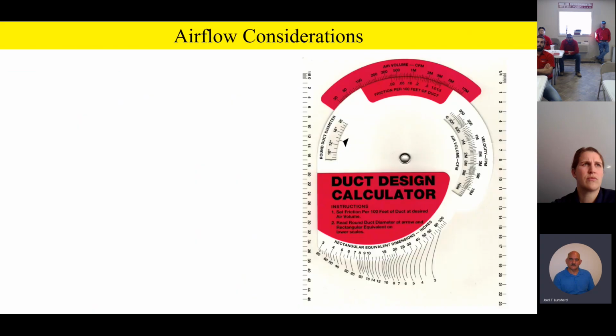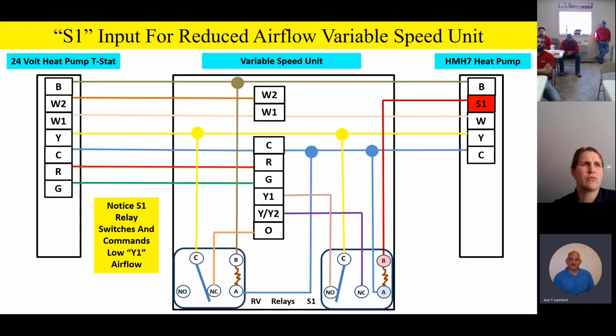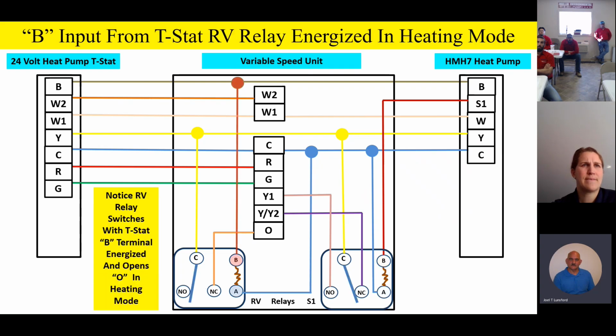So that's why we have that RV relay there. Let me back up. That's why we have the RV relay. In the cooling mode, we energize the O terminal on the indoor unit. In the heating mode, bang, we break that O terminal to tell the indoor unit we're in the heating mode. Any questions or comments on the relay logic that we're looking at with the relays and the indoor product and the outdoor product? Any questions or comments on it?